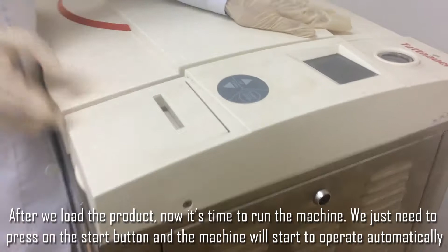During the operation, the first step is air will be sucked out from the autoclave. This is to prevent any interference in the heat transfer process. The removed air will be replaced with steam. Then, the steam will be heated until it reaches a temperature of 121 degrees Celsius. The temperature will be maintained for 15 minutes and this is when the sterilization cycle will begin.